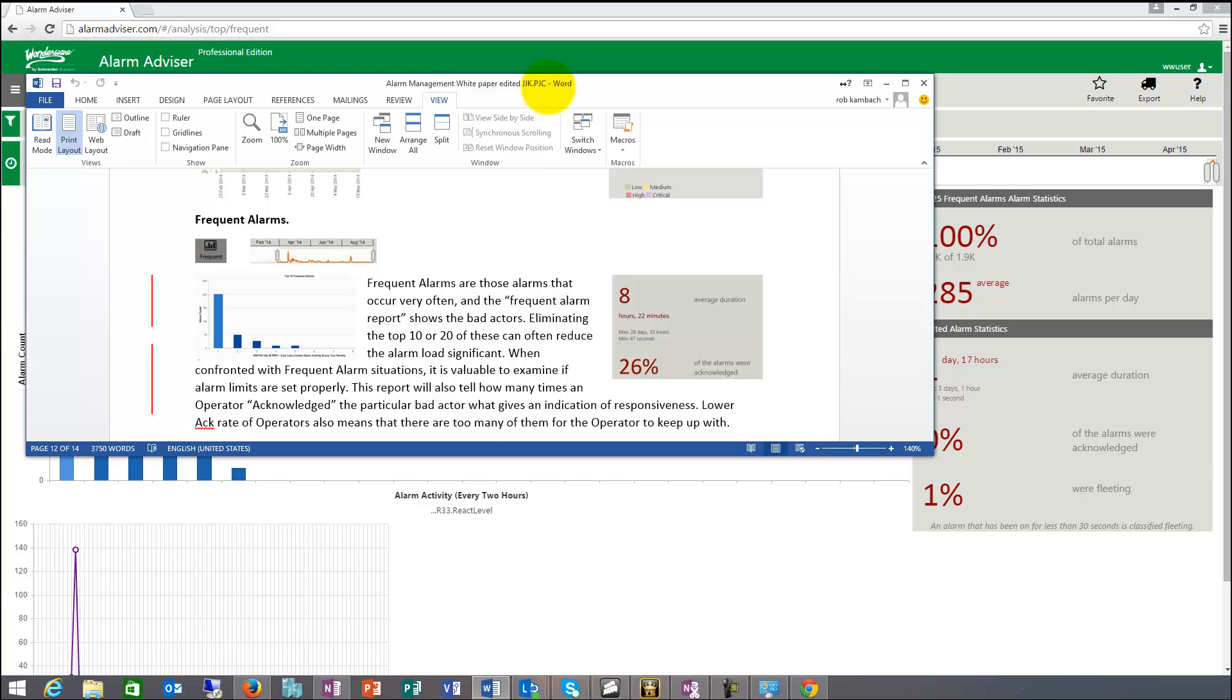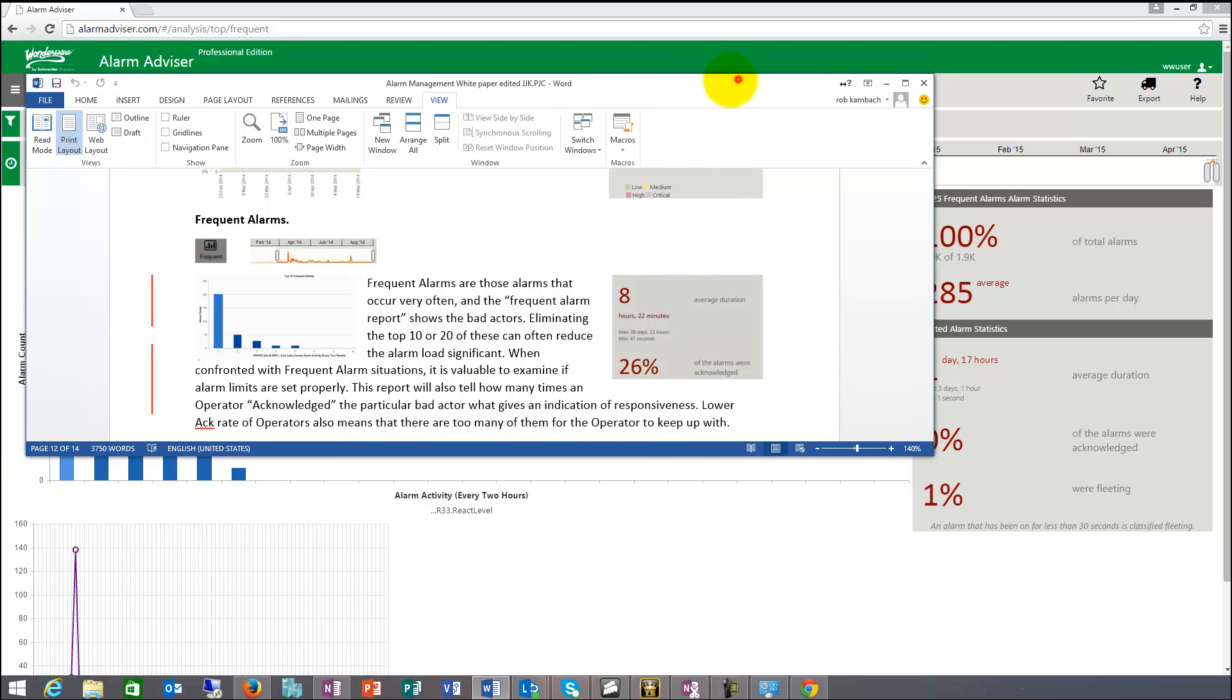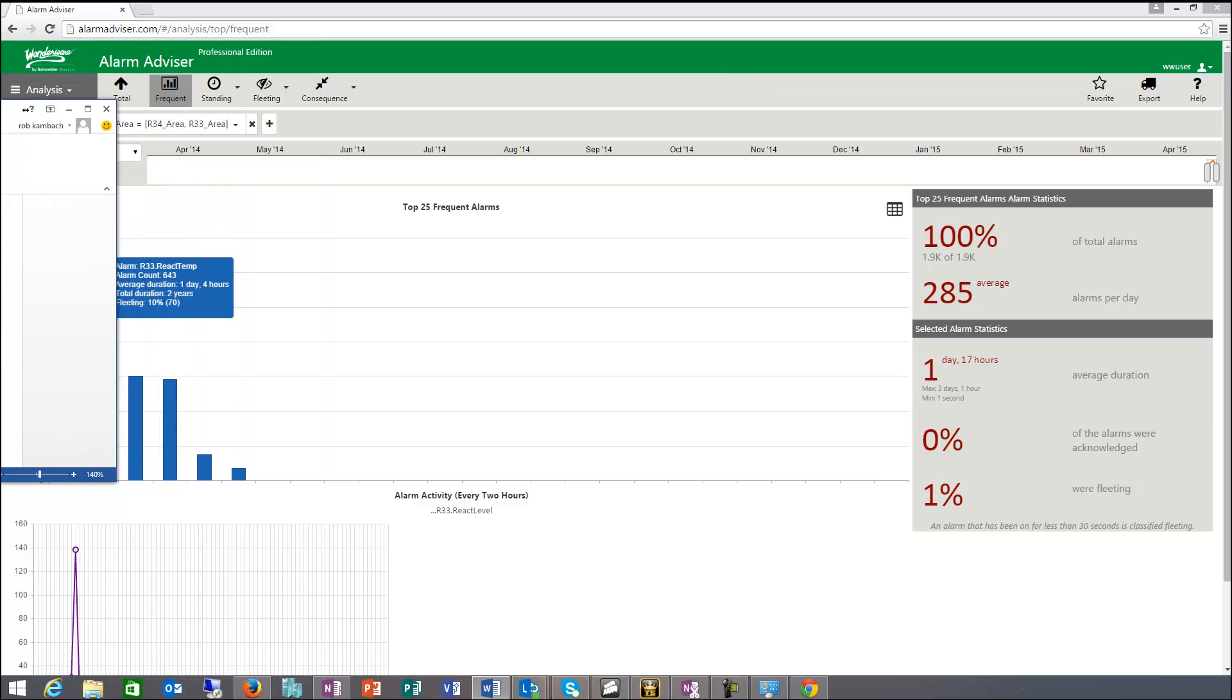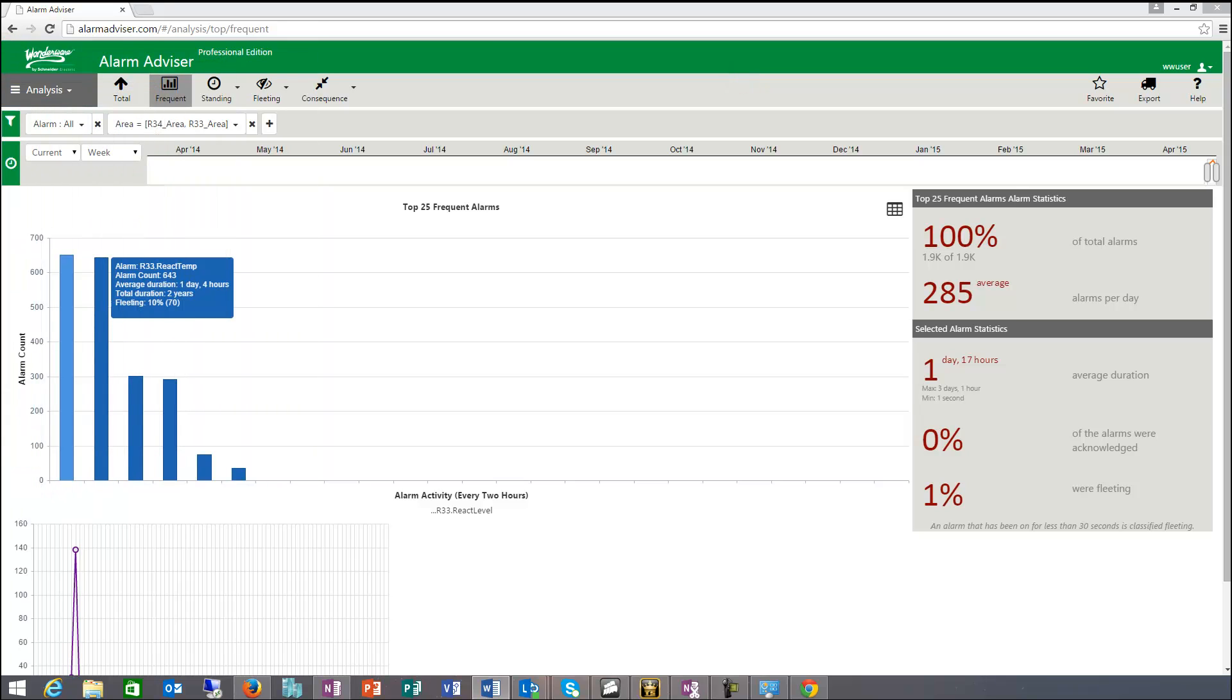Eliminating the top 10 or 20 of these can often reduce the alarm load significantly. When confronted with frequent alarm situations, it's valuable to examine if the alarm limits are set properly in this case. So this report will also tell how many times an operator acknowledged the particular bad actor, what gives an indication of responsiveness. And not only that, lower act rates could also indicate that operators have too many alarms and basically are unable to keep up with.